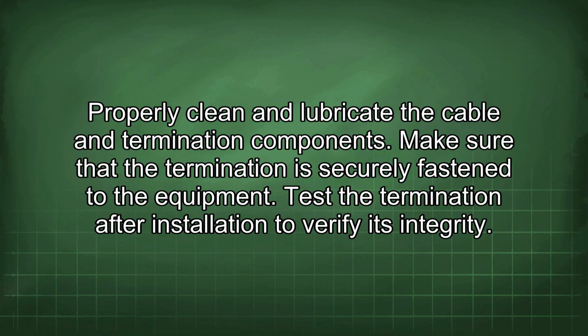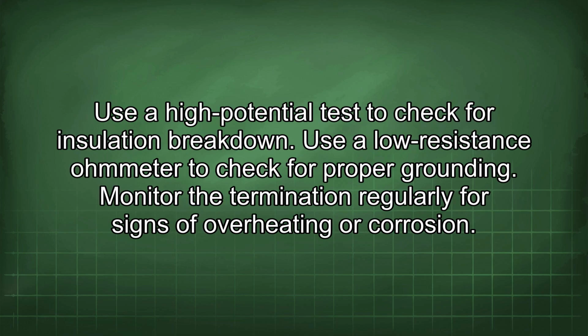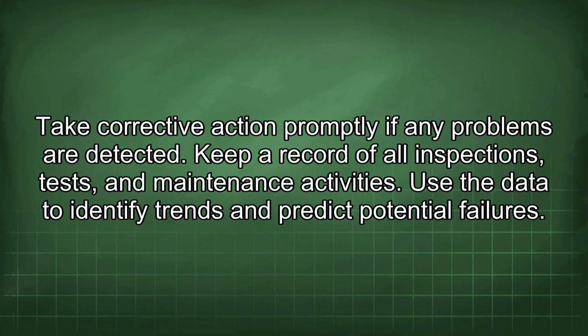Test the termination after installation to verify its integrity. Use a high potential test to check for insulation breakdown. Use a low resistance ohmmeter to check for proper grounding. Monitor the termination regularly for signs of overheating or corrosion. Take corrective action promptly if any problems are detected. Keep a record of all inspections, tests, and maintenance activities. Use the data to identify trends and predict potential failures.